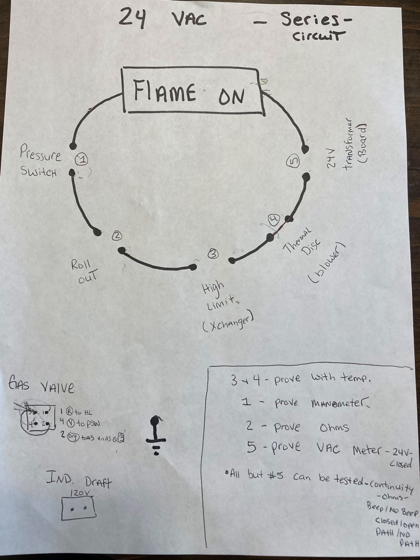So this safety sits right in there on a temperature. Let's say the temperature is 180 degrees. If I am failing on that switch and I prove with my meter through continuity, right? I've put a lead on continuity across the whole switch, one on one side here and one on the other side here. And I found that I did not have a path. I'm in a real no beep situation. I can't immediately fail the switch. I have to prove, is that switch lying, or is that truth, and is it indeed getting over 180 degrees?